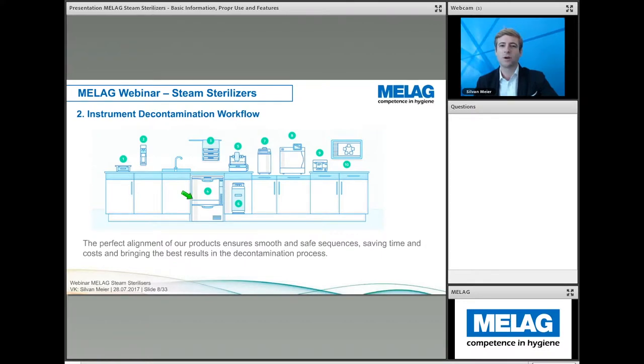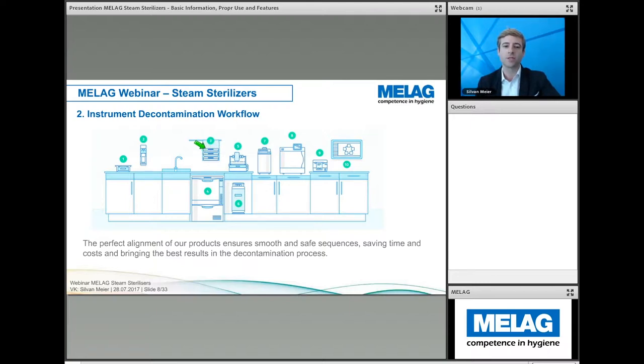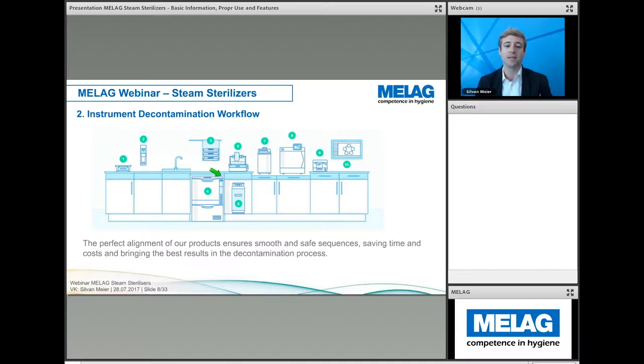Number four is our Melatherm, where we start with automatic washing and disinfection. It has integrated process media — the detergents — and also active drying, meaning all instruments come out dry. They can be inspected and cared for with lubricants. After that, they can be placed in Melastore boxes or safely wrapped in pouches and sealed with our sealing machine, Melaseal. For the whole process, we use demineralized water with our water treatment system.